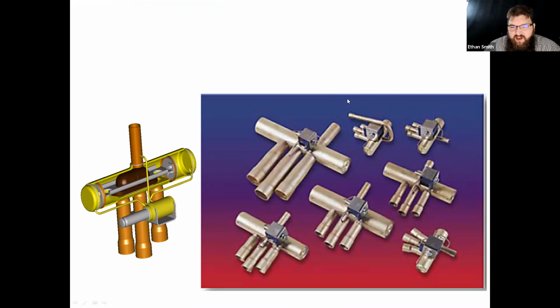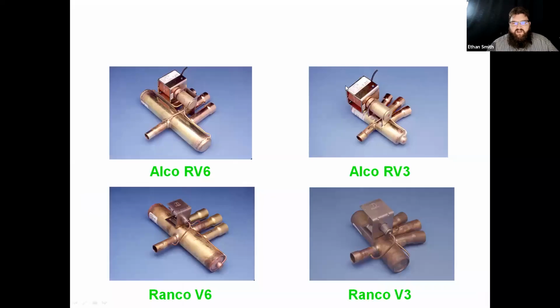Okay. There's various types of reversing valves out there, guys, all shapes and sizes. That's a big mama there. But the ones that are probably the worst to change out are these guys. They're just miserable. When guys go to change these reversing valves out, there's usually an easier way to do it, and I'll go into that when we go into repair, though. But there's all kinds of varieties of them out there. At the time that I wrote this class, these were the current valves used in Trane American Standard equipment. Just kind of depended on your tonnage which one you got. But they all operate pretty much the same way.